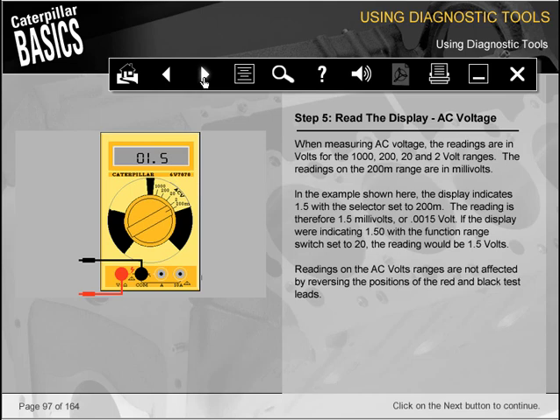When measuring AC voltage, the readings are in volts for the 1000, 200, 20, and 2 volt ranges. The readings on the 200M range are in millivolts. In the example shown here, the display indicates 1.5 with the selector set to 200M. The reading is therefore 1.5 millivolts or 0.0015 volt. If the display were indicating 1.50 with the function range switch set to 20, the reading would be 1.5 volts. Readings on the AC volts ranges are not affected by reversing the positions of the red and black test leads.